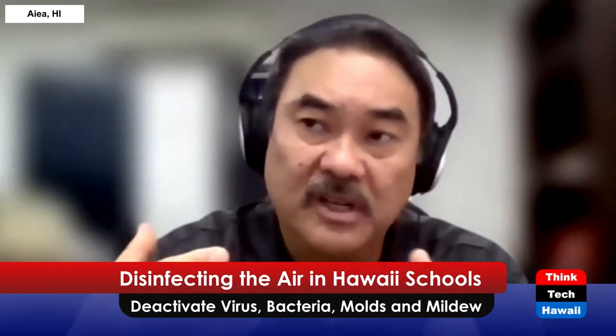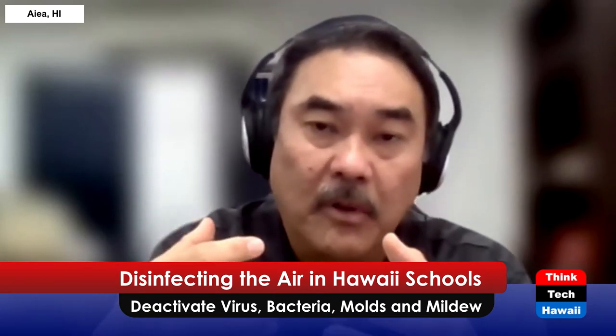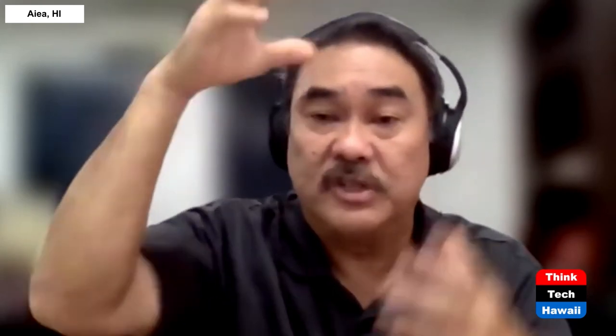So when we do an install, included in our price is a commissioning of the device, which means we take this meter and check at 3 feet off the unit to see if we're getting certain energy strengths. The standard set was about 310 microwatts per centimeter squared off the front, and that shows you're starting to deactivate viruses.